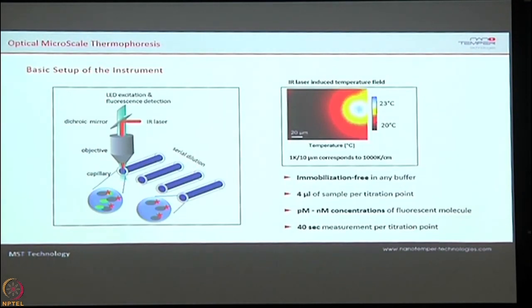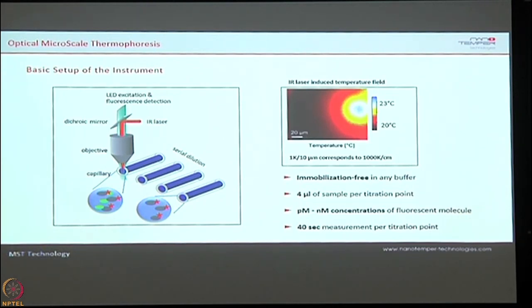With this basic principle of thermophoresis, we built an instrument with two important things: one is a laser that creates a temperature gradient for thermophoresis, and one of the binding partners is fluorescently labeled. There is a fluorescent detection unit, and the biggest advantage is you are not immobilizing anything. You directly determine the binding affinity in buffer, requiring only 4 to 5 microliters of sample. Normally you do a dilution series of 12 to 16 dilutions, and every dilution takes 40 seconds to scan.